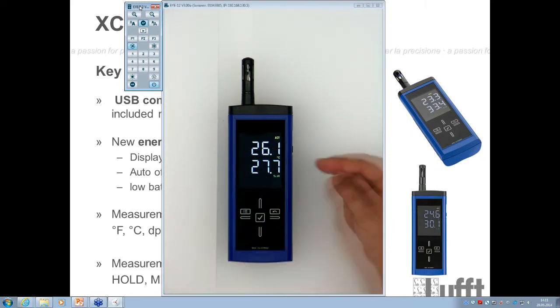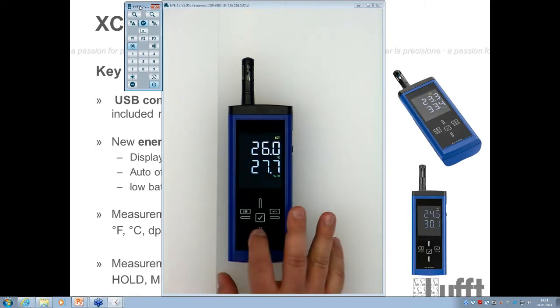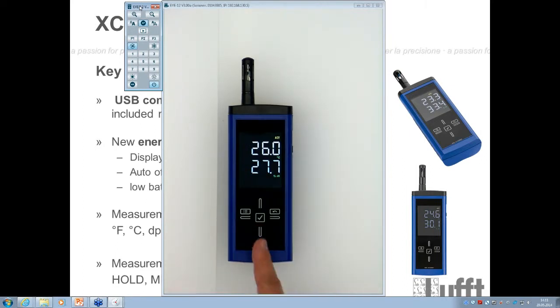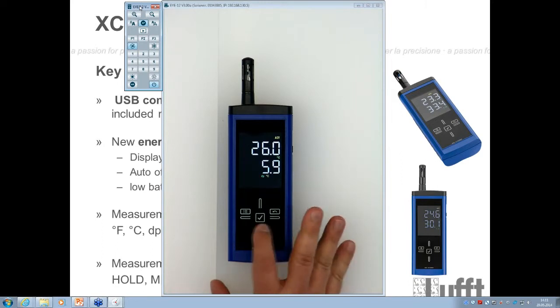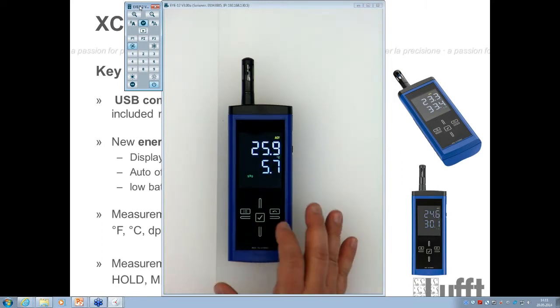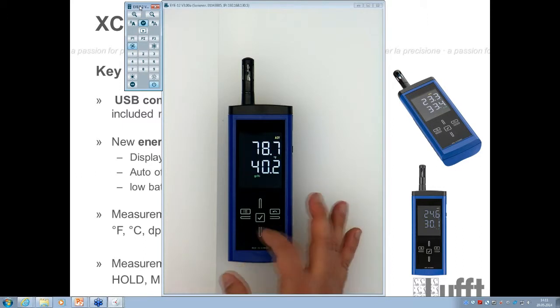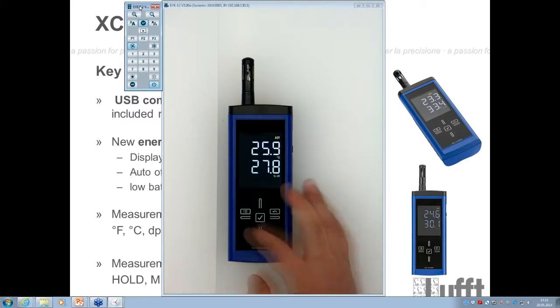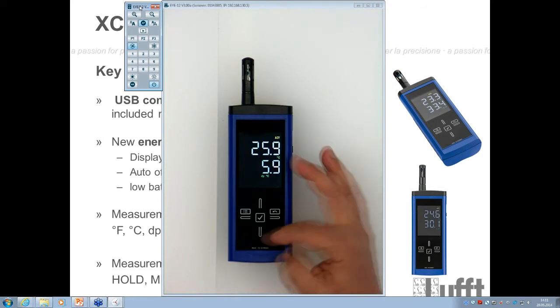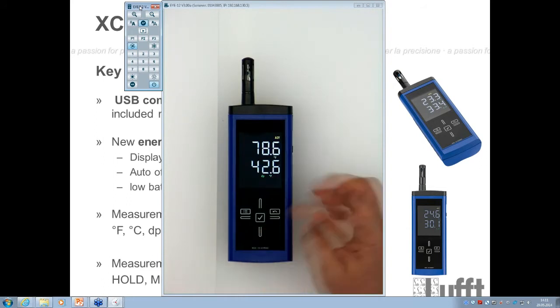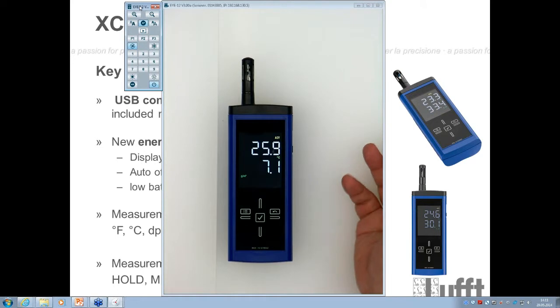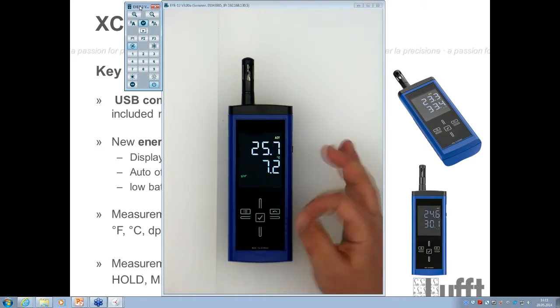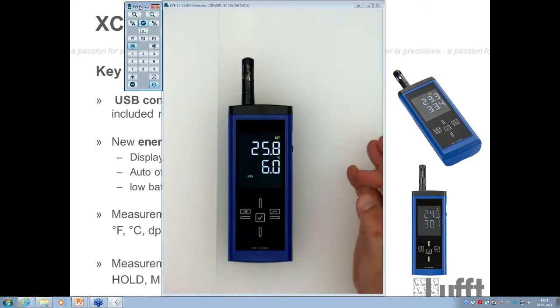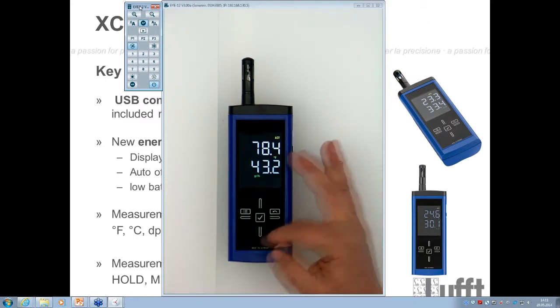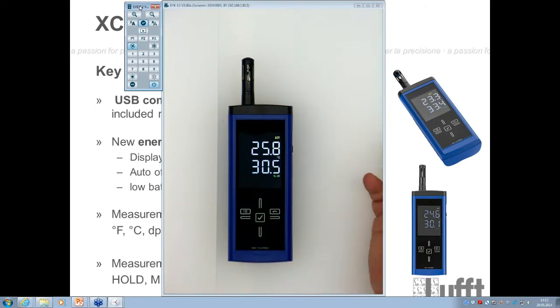Then if you want to switch the second segment, you use the up-down key here, this one. With this key you can switch between different values on the second segment, for example humidity here, or dew point in Celsius degree, or dew point in Fahrenheit, or absolute humidity in grams per cubic meter, or the mixing ratio in grams per kilogram, or in grains per pound. So those are the possibilities.